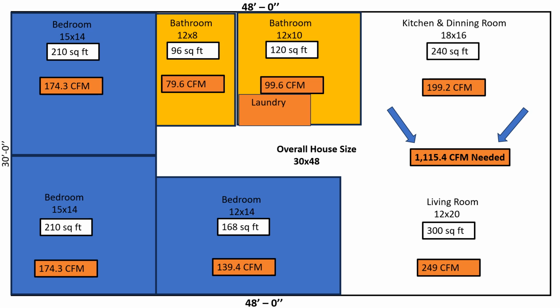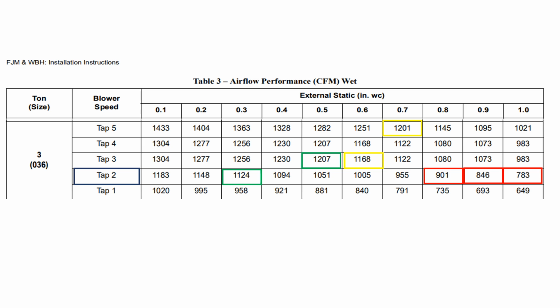Well, if you open up your manual and turn to, usually between page 11 and page 14, you'll see this table number 3 on this particular piece of equipment, ICP. You're going to see external static pressure, the ton size, and the blower speed, and these numbers here represent your static pressure. Now, let me share with you that our older model, as of 2 years ago, was a FEM4X. That FEM4X only went to 0.6.